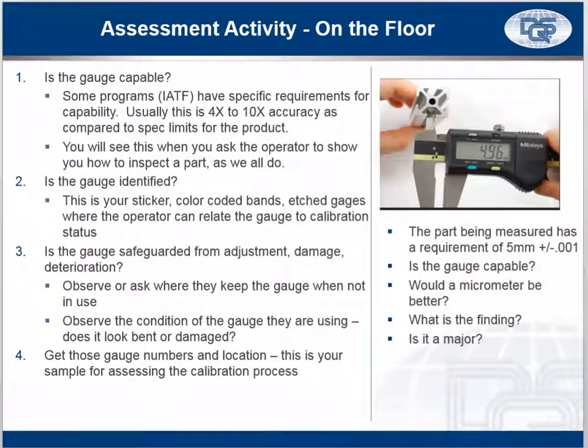So the first thing you're going to see out on the floor is whether the gauge is capable. Some programs might have requirements for accuracy, like the MSA manual spells out some accuracy type requirements. Most programs do not. As a rule of thumb, you'd want to see 4 times to 10 times more accuracy in a transfer standard from what's being measured. So we'll talk about that with this example over here. You want to have the operator show you how they inspect the part. That's another way of knowing whether the gauge is capable or not.